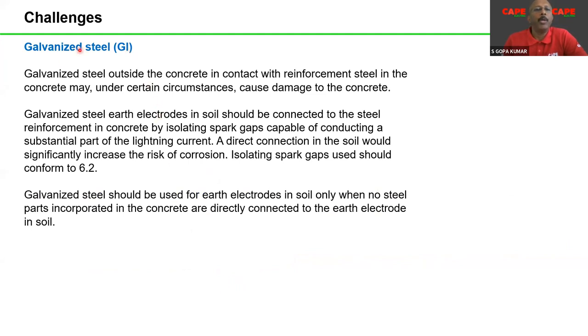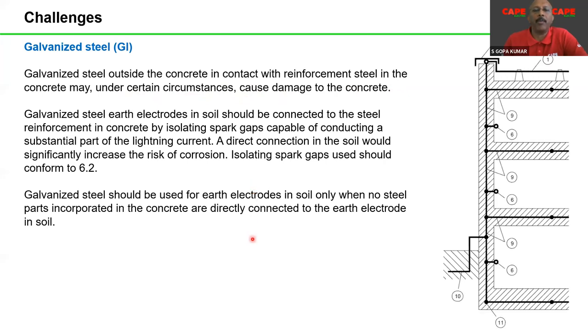Now, further, these are the further challenges. For example, galvanized steel outside the concrete, in contact with reinforcement steel, may under some circumstances cause damage to concrete. What does it mean? You have the building here. Now, item number 10, we are taking a connection from outside the concrete to something in soil. And if you are using galvanized steel in this soil, it will be forced into accelerated corrosion. Galvanized steel will disappear within a few years, or within a few months. So galvanized steel electrodes in soil should be connected to the steel reinforcement in concrete by an isolating spark gap. That means a direct connection in the soil would significantly increase the risk of corrosion. An isolating spark gap should be used.